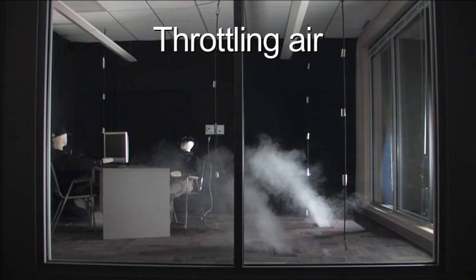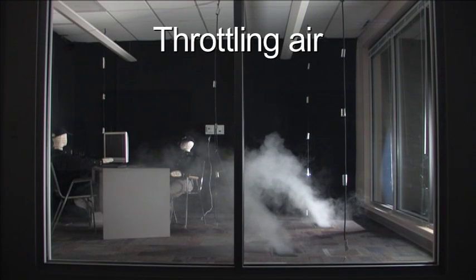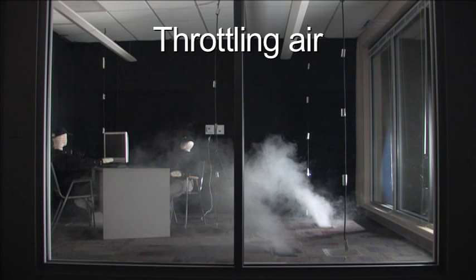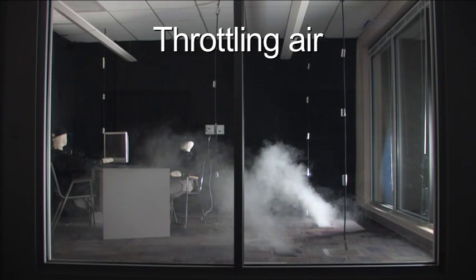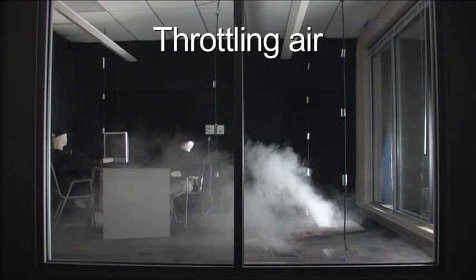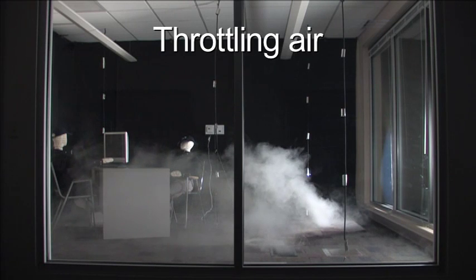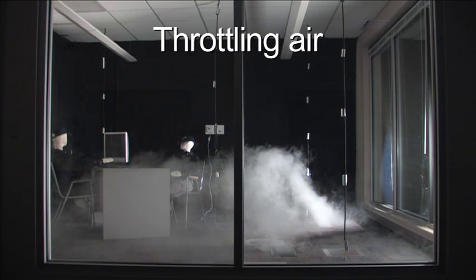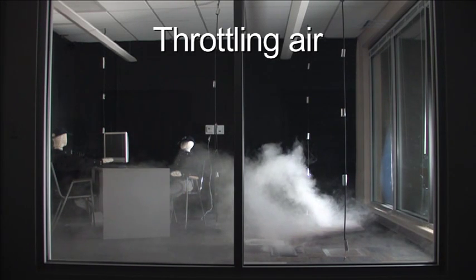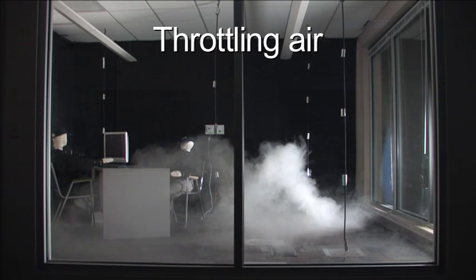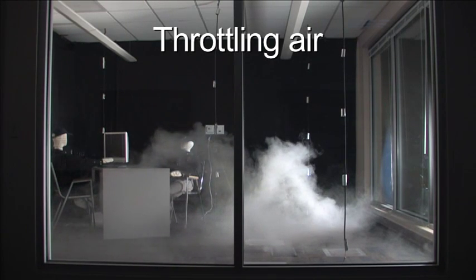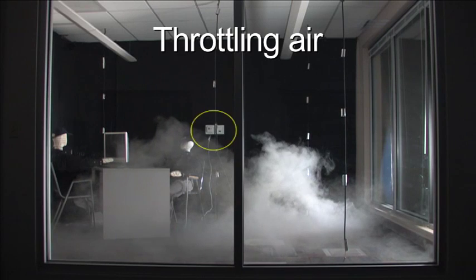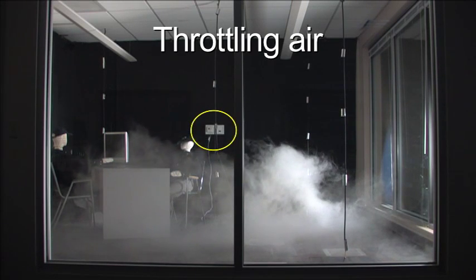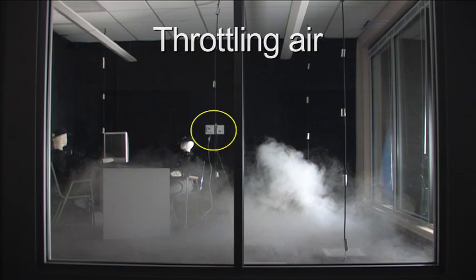As you see, the cold air, represented here by smoke, pools on the floor with virtually no mixing into the top half of the occupied zone. We believe this contributes to cold draft complaint calls. This pooling of cold air not only affects occupant comfort, it inhibits thermostatic control. Note that most of the mixed air pools below the thermostat.